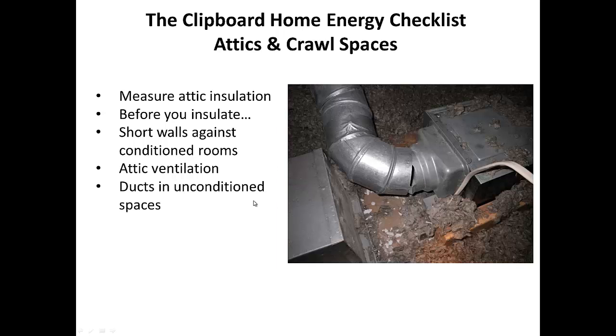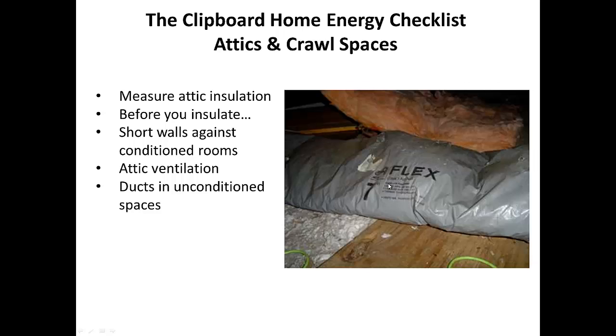Another thing to look for are ducts in unconditioned spaces, and whether it's a return duct or a supply duct, this is a place where hot air in the summertime or cold air in the wintertime gets right into your ventilation system, your HVAC system, and causes real energy problems. Another thing to look for is the ductwork in your attic space where it's been trampled on over time. Somebody got up there, a contractor or a homeowner, and stepped on it. So the room that's being supplied by this flex duct is not getting its fair share of energy right now.